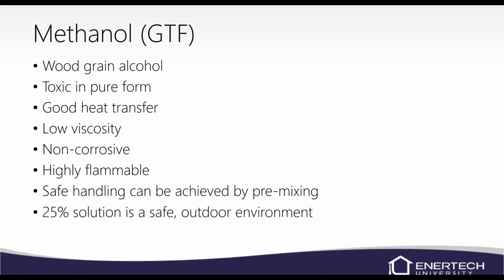You will have to pre-mix the antifreeze in the field. My recommendation is do it outside. If you do it inside in the basement, you've got a gas water heater in there, you could cause a thermal event, let's put it that way. You could cause a fire down there. And the thing about methanol and ethanol is it's like the Ricky Bobby fire, the invisible flame. So you're not going to see it when it's burning, and hopefully it's not on you. So just be really super careful with methanol and ethanol. You'll normally get it in a 50% solution, so it's flammable, and you're going to have to mix it in the field. So do it outside if at all possible.